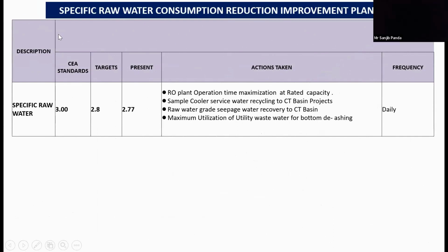Thank you. Then we have taken some measures on the reduction of specific raw water consumption: RO plant operation time maximization at rated capacity, which effectively reduces our makeup water requirement. Sample cooler service water recycling to cooling tower basin project. Raw water grade seepage water recovery to the basin through suitable measures. Maximum utilization of utility wastewater for bottom ash handling. Next, ma'am.